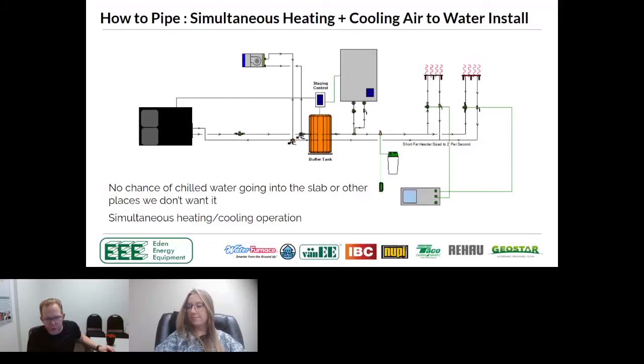So what Sarkis is referring to is I have a supply and I have a return one. And really the only reason I'm concerned about that, Sarkis, is this boiler. So if I didn't have a boiler here, if I didn't have any means that I could potentially heat this tank to a crazy high temperature, I wouldn't be so concerned about diverting. I'm just trying to make sure that I'm diverting through the system completely so I've got complete flow happening where it's not trying to do anything too crazy. Trying to think for all the things that we can't account for.